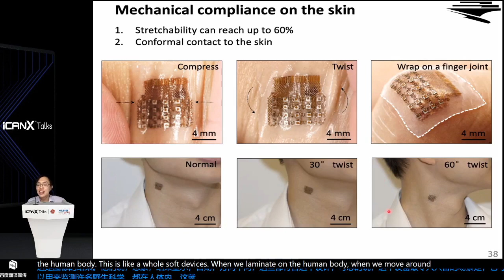I would say the most exciting thing about this wearable ultrasonic device is that it can be used to monitor a lot of vital signs in the human body, right? This shows how soft this device is when we laminate it on the human body. When we move around, it does not delaminate, clearly showing the minimal mechanical loading on the human body. How deep can the ultrasound penetrate? With a transducer size of around 0.9 millimeter by 0.9 millimeter at a frequency of 3.5 megahertz, it can penetrate about 40 millimeters. And this penetration depth is tunable by the size, the frequency, and the power, right? In our published results, we can penetrate about 14 centimeters inside the human body, and that means we can have access to almost every human organ.